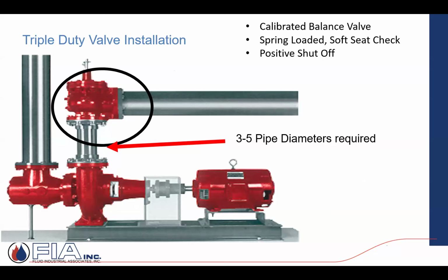Another accessory on the discharge side they're going to call a triple duty valve. Triple duty, 3 functions. I'm trying to explain at the top, but it can act like a balance valve, a throttling valve, balancing, kind of bringing that pump in line if need be, if it's oversized. It acts like a check, or spring-loaded soft-seated check. And then it can also act like a service valve, so you can close it right down and isolate the system side from that pump.